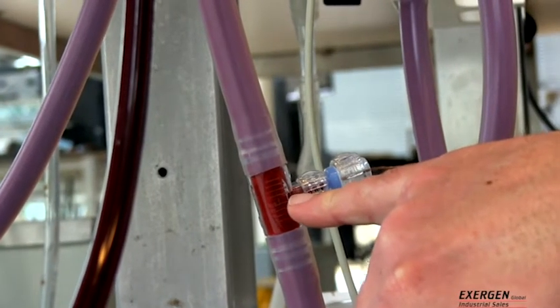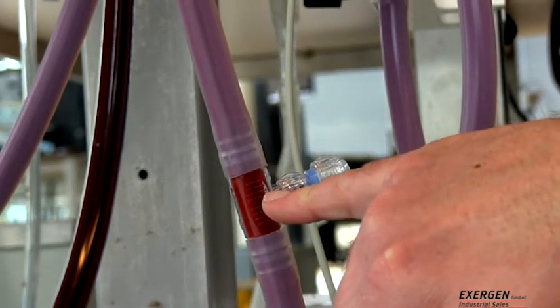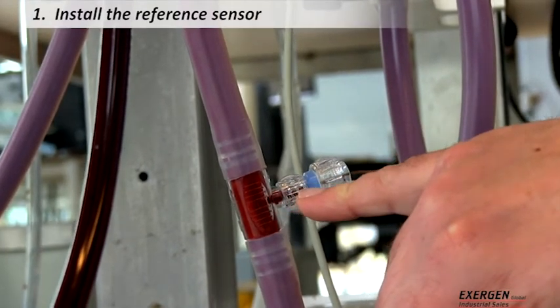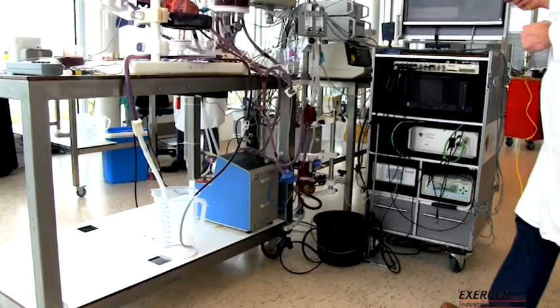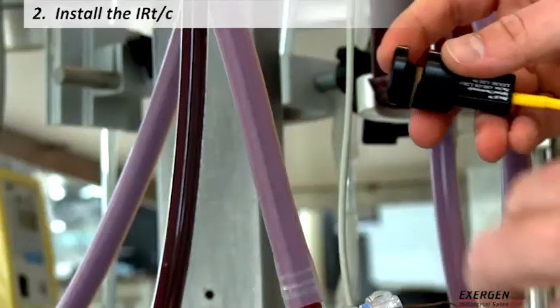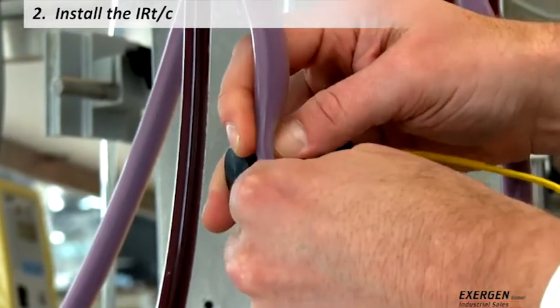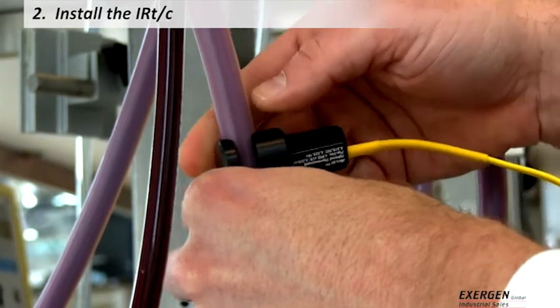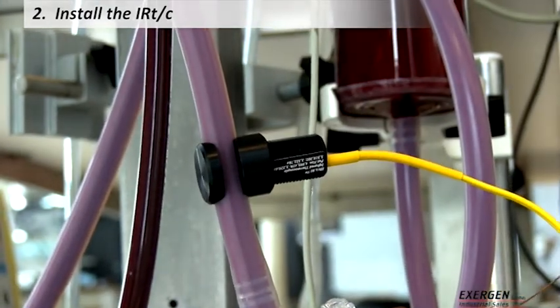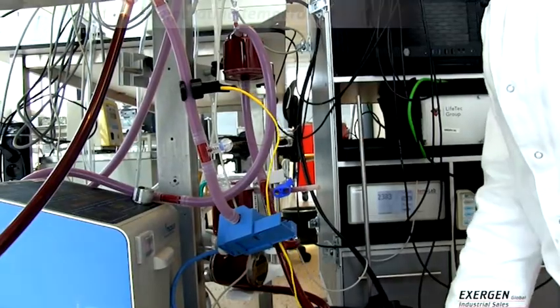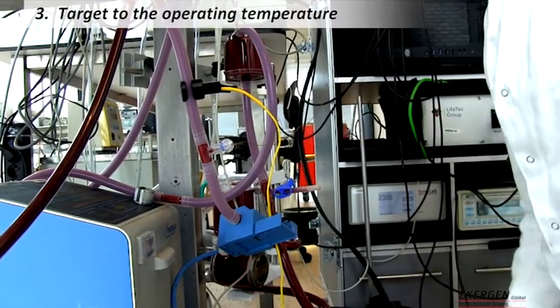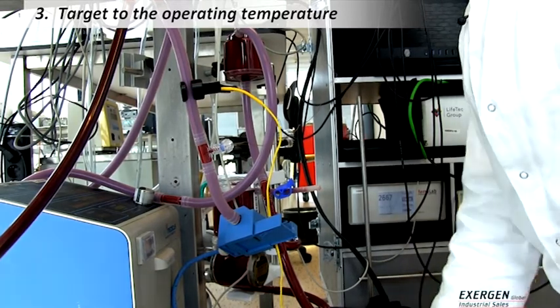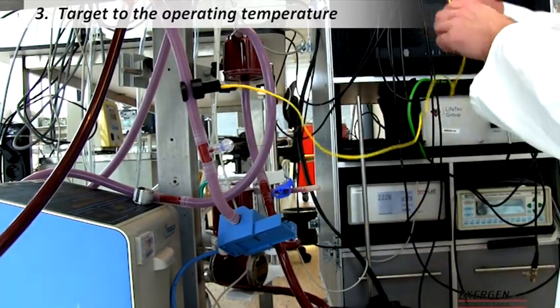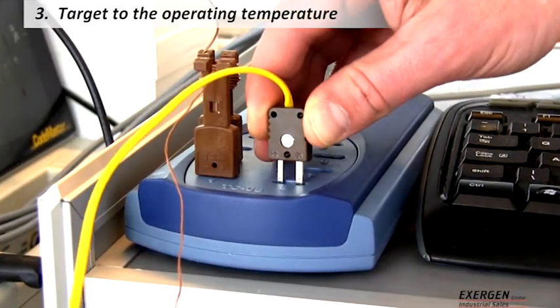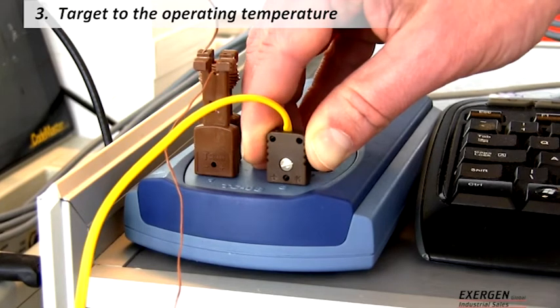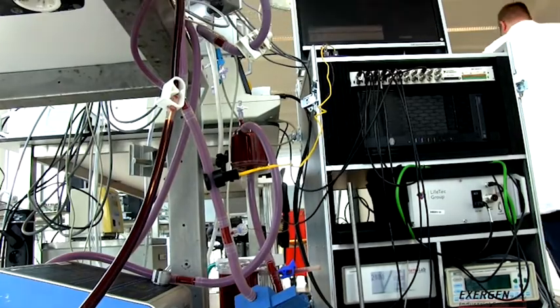For the initial calibration, a reference sensor in the fluid is required. Step 1. Install the reference sensor in the fluid. Step 2. Install the IRTC and align to view the desired target. In this case, our convenient mounting clip is used to mount the IRTC on the tube. Step 3. Bring the target to operating temperature, in this case 38 degrees Celsius, as indicated by the reference sensor. Allow the sensor and the clip to reach steady state temperature for approximately 10 minutes.